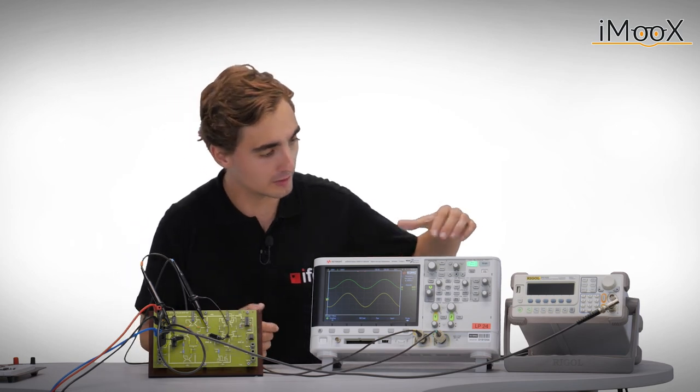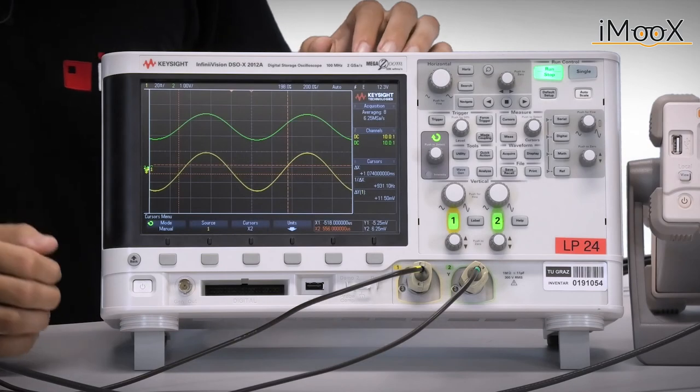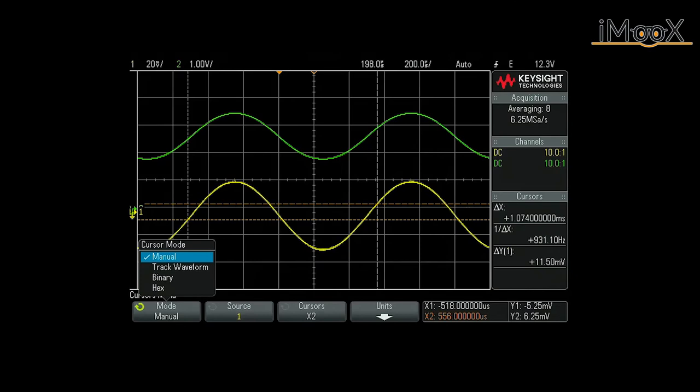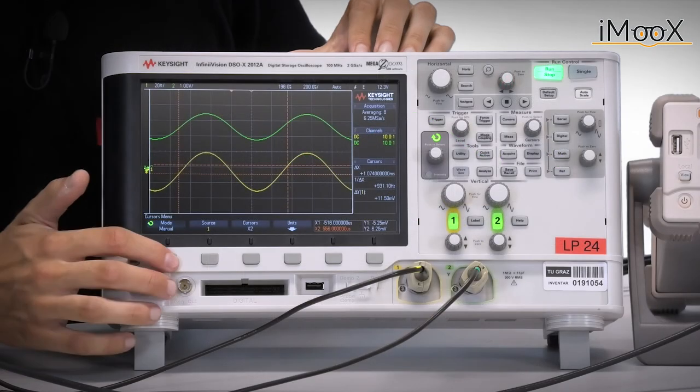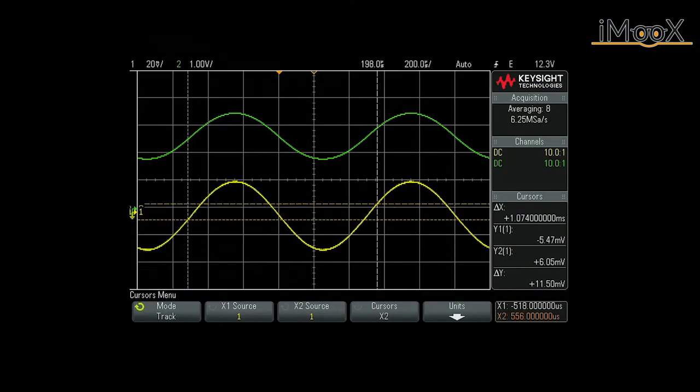A manual way of measuring characteristics of a waveform is also available when using so-called Cursors. Again, there are different modes available in the Cursor menu, from a fully manual cursor mode where X and Y-axis have to be defined separately, to a Tracking mode where only the X-axis is defined and the Y-axis is obtained from the signal.